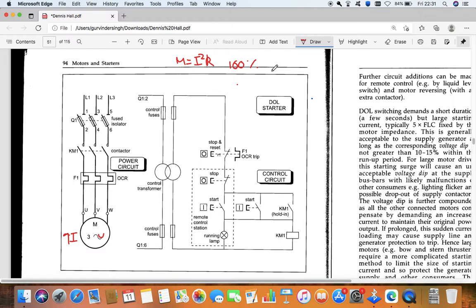For that we have many starters, such as the star delta starter, the auto transformer, and one electronic starter, that is the soft starter. Today I am going to explain the simple starter, that is the DOL starter. Keep in mind that the DOL starter does not reduce the starting voltage, so if you start a motor with it, it will draw the full starting current. So the DOL starter is only used for smaller motors, not bigger ones, because on a bigger one it will cause a voltage dip to other consumers and also flickering.